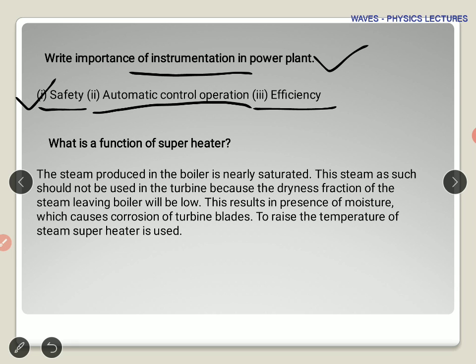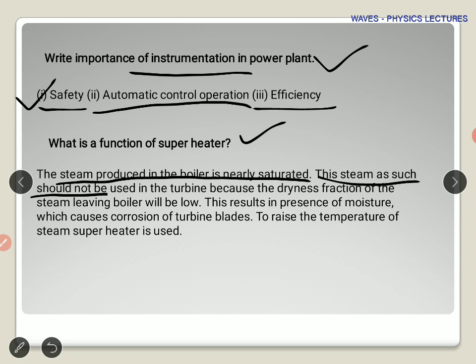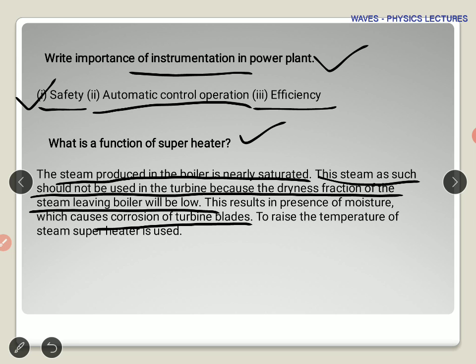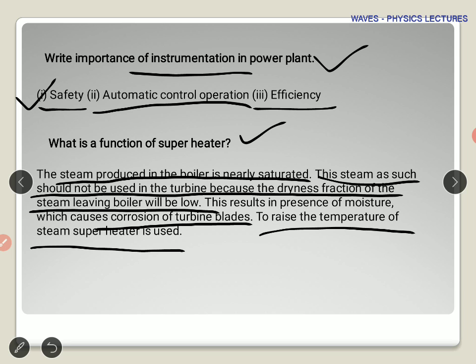What is the function of a superheater? A superheater is a system attached to the boiler. The steam produced in the boiler is nearly saturated, and this steam should not be used directly in the turbine because its dryness fraction is low. If the steam is not totally dry, moisture is present, which can cause the turbine blades to rust or corrode. The superheater raises the temperature so that moisture is minimized, protecting the turbine blades from corrosion.